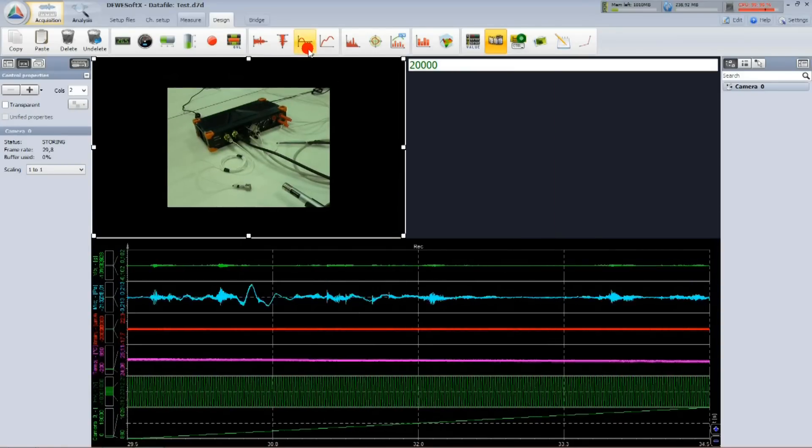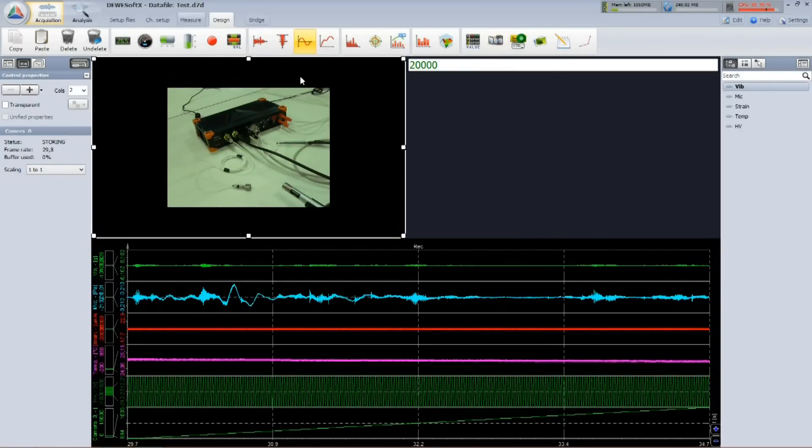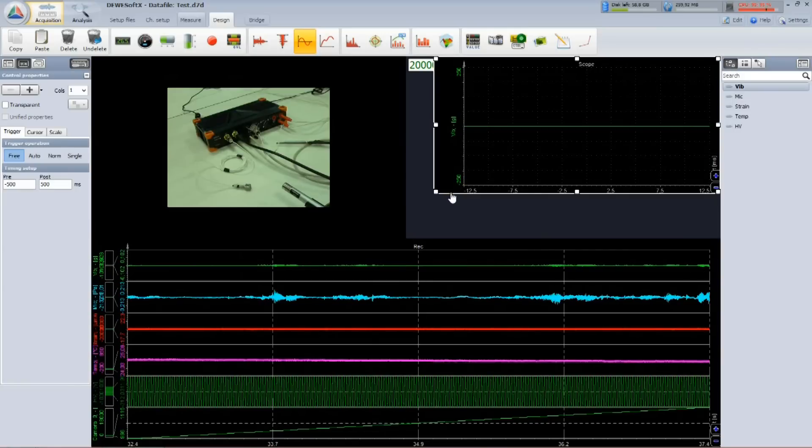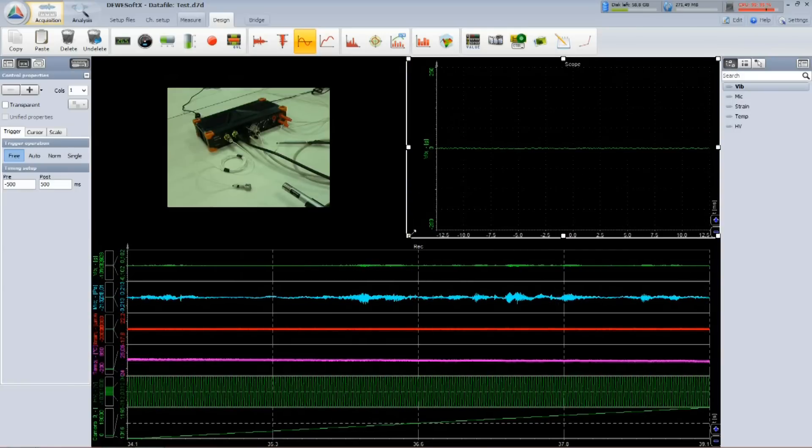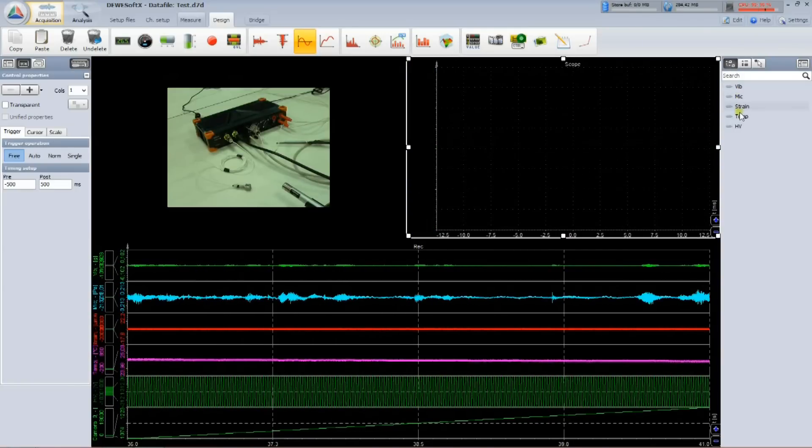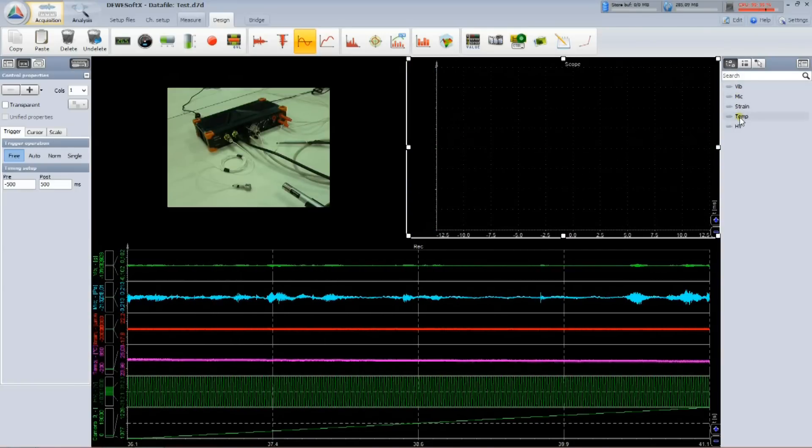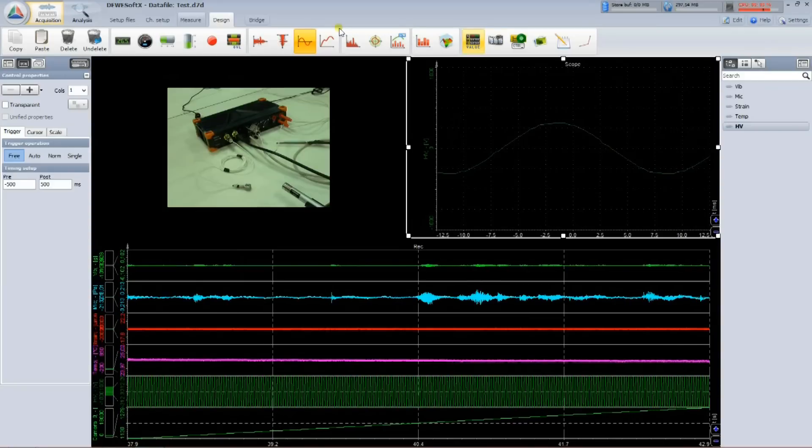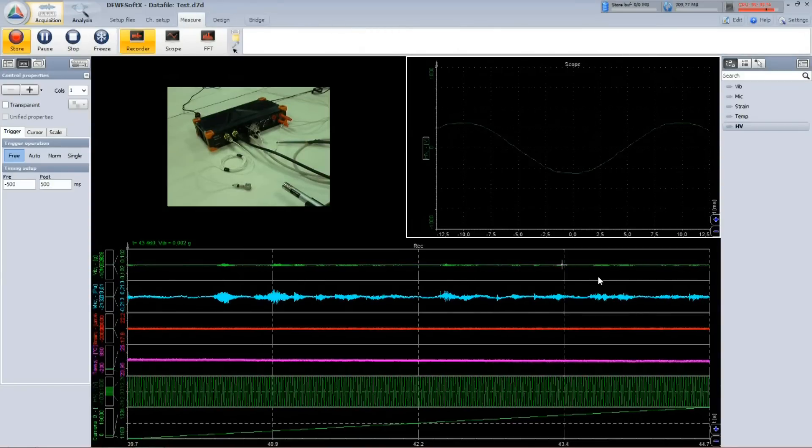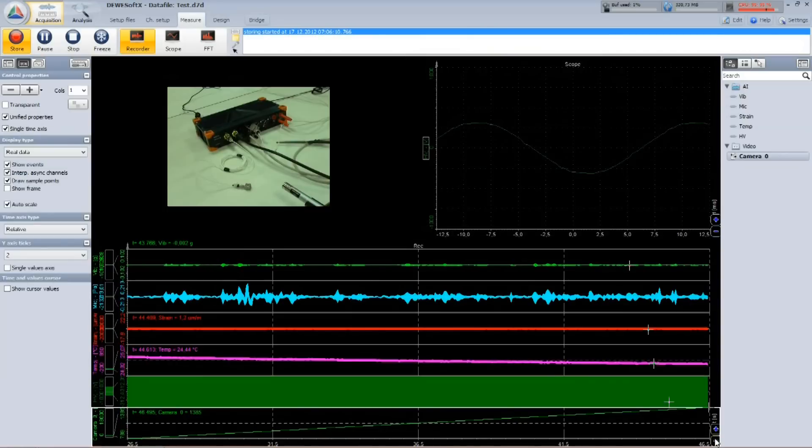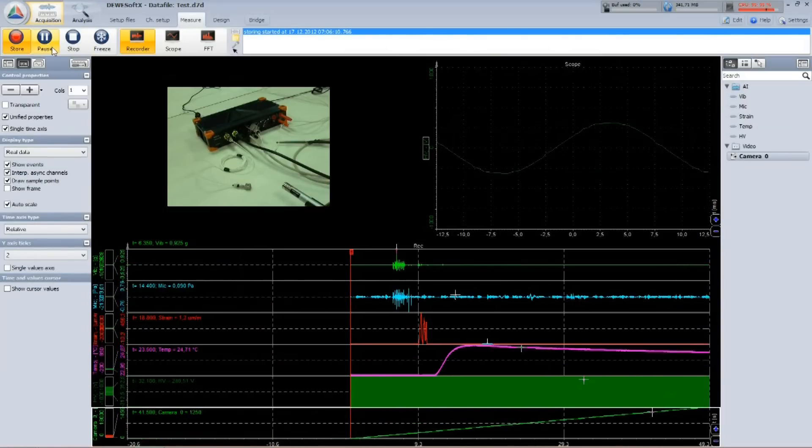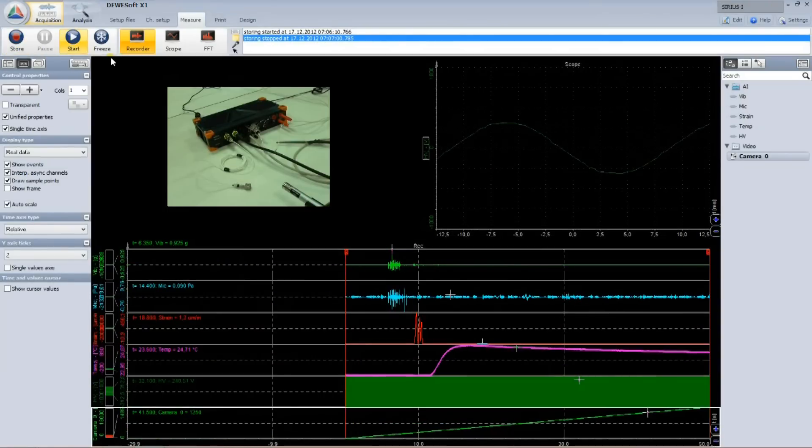Let's add another scope. From the right side, I can select the channels to show in each display. While arranging the displays, Dewesoft stores the data all the time, and I can zoom out to see the entire recording. After pressing stop, I can analyze the data.